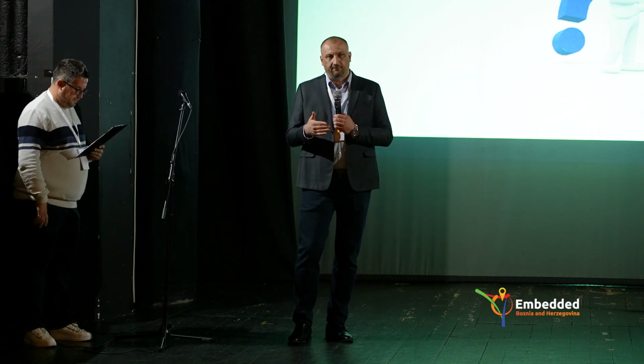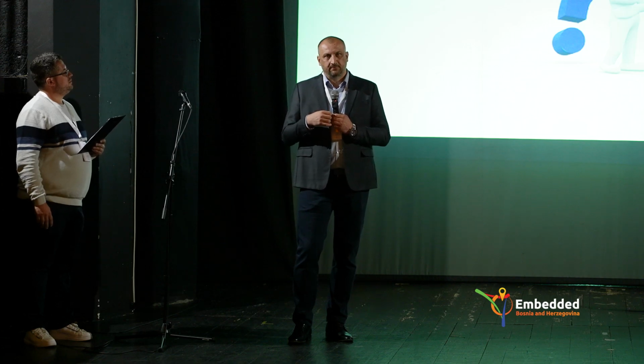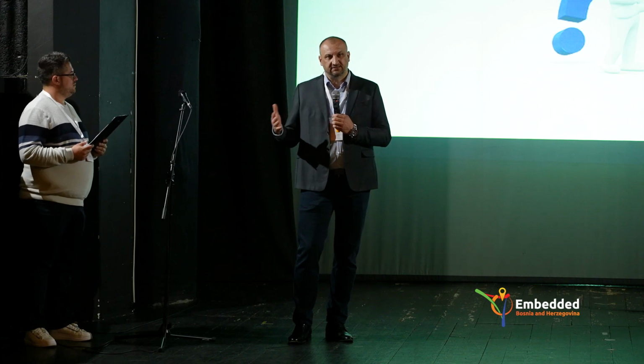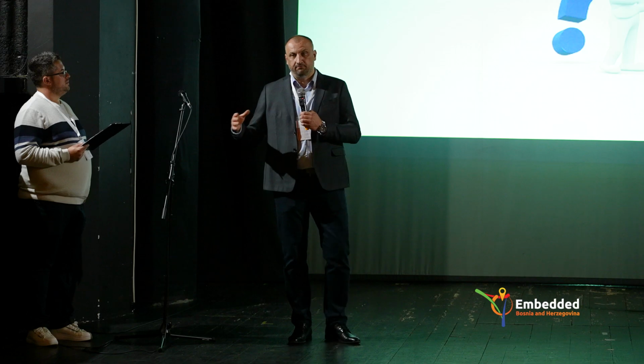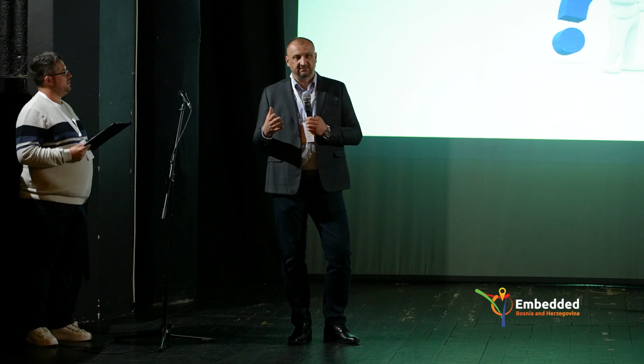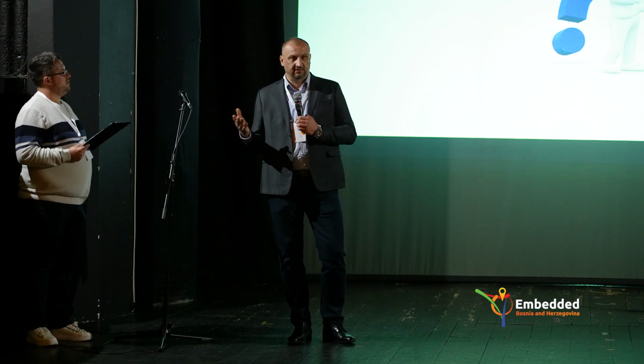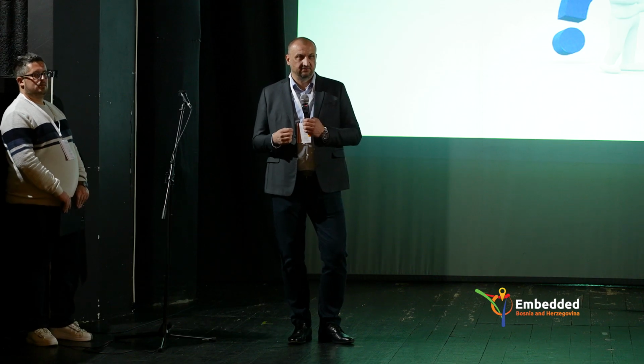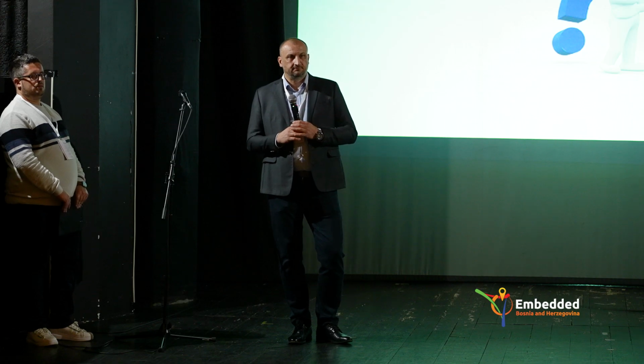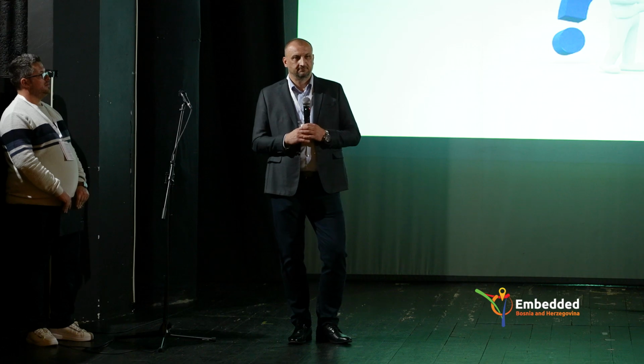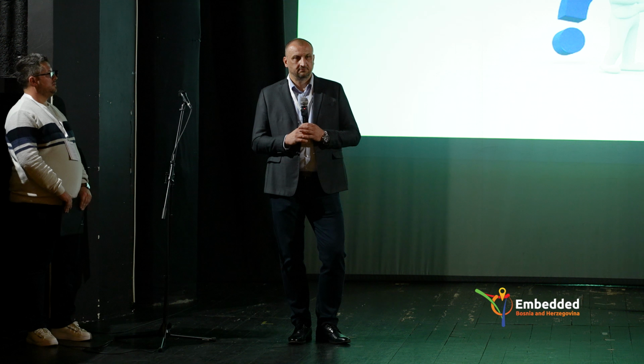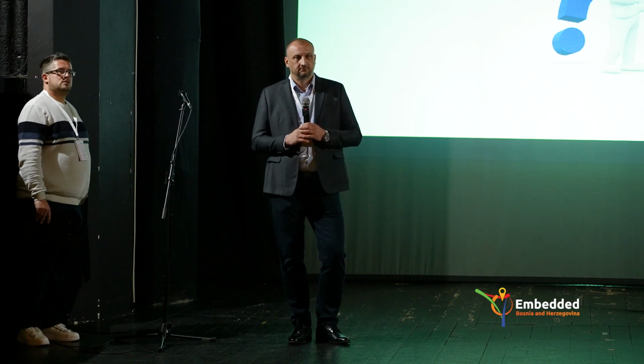So, if you promise something, but you cannot achieve that level of reliability, and there are no other options to reduce the risk, no options to design further, or no options to include more high integrity components or something, then you also have to analyze in the risk management what is the cause of the failure and the consequences. So basically, if the risk is low, we can't mitigate it because it's not really possible, and the damage, especially for a human, is not that big. So we can say, okay, this is not that big of an issue. For example, if we have an increase of the voltage and this just damages the equipment but doesn't harm the human, we can say this is acceptable for us and the regulatory will accept it.